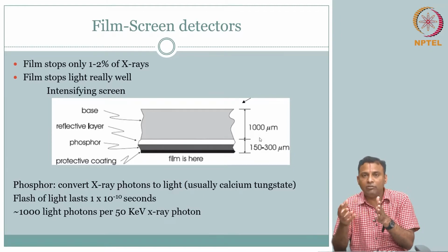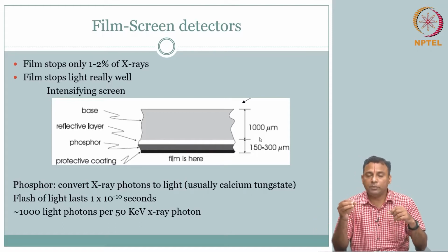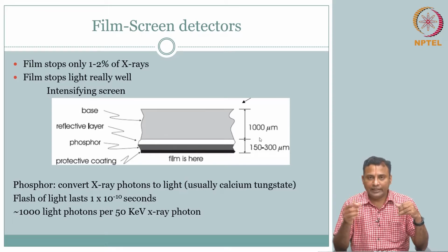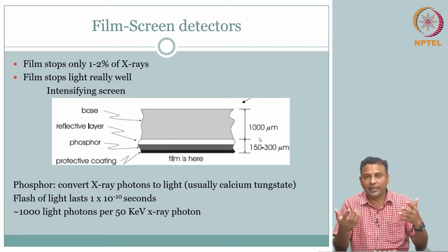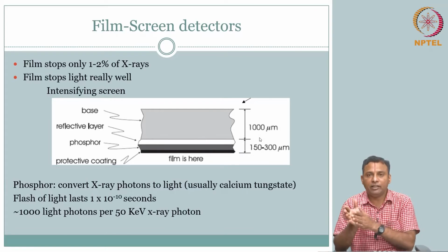The material's ability to convert one energy to give many photons. So, the speed of screen is typically used to refer to this conversion. Why? Because if I have high speed of screen, that means it takes little time, because more photons are created, the conversion is high, and more light photons are generated. If more light photons are generated, the film can get exposed quickly.